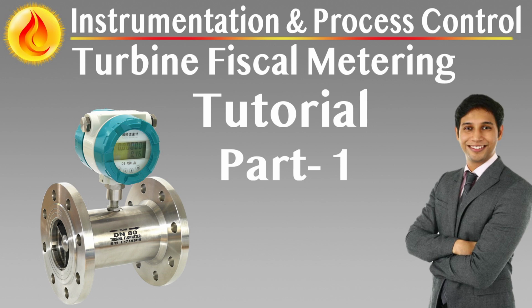Inlet header and sampling logic. The inlet header forms the pre-measurement boundary and is embedded with critical instruments, pressure and temperature transmitters, gauges, and optional sampling lines. These are designed to be upstream of the metering and proving loops unless specified otherwise. The system must allow for safe, representative fluid sampling, particularly for density checks and custody quality analysis. The integrity of the inlet header instrumentation is pivotal in early anomaly detection and plays a direct role in flow control algorithms.